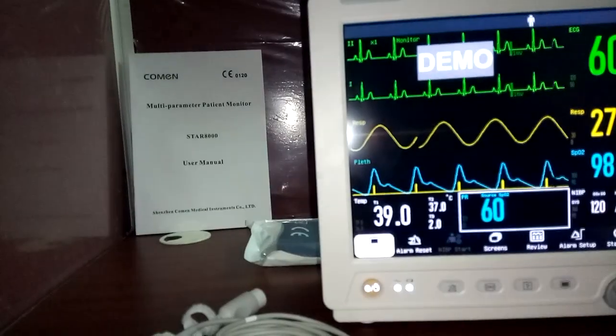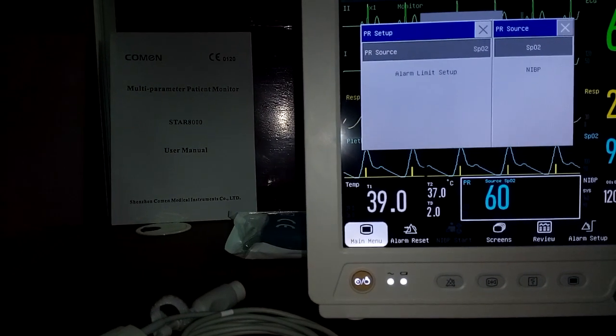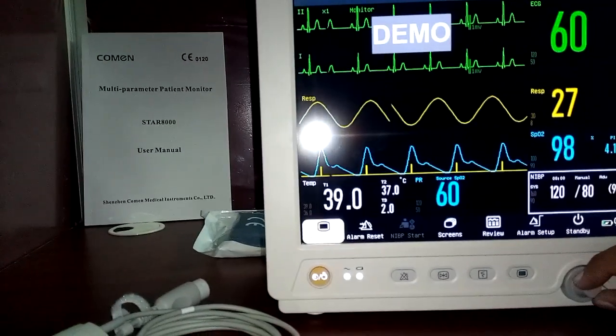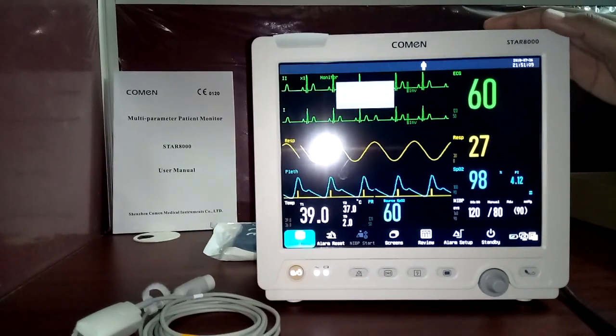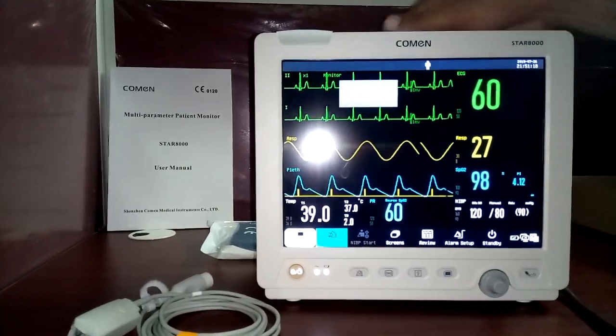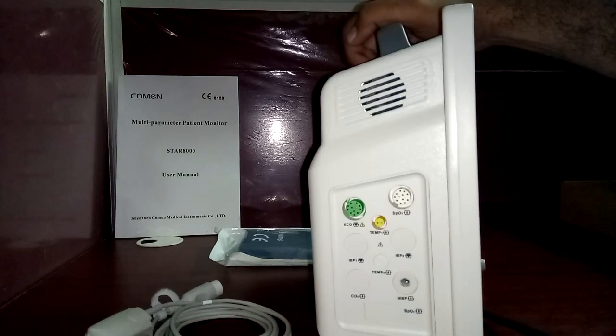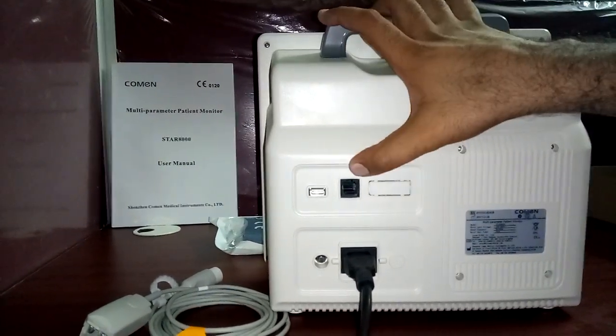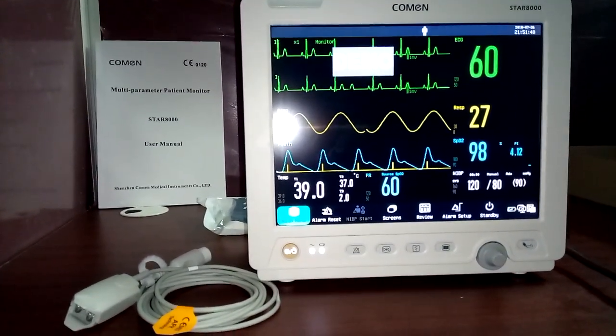That completes the detailed demonstration. The temperature menu lets you set temperature alarms, and the pulse rate menu lets you set pulse rate alarms and select the pulse rate source — ECG, SpO2, or IBP. The Comen STAR8000 is a 12.1-inch high-end monitor. Touch screen is an optional upgrade; the standard knob control is easy to use. It is a lightweight monitor suitable for transport ICU and general ICU use, with a USB port and central monitoring port.